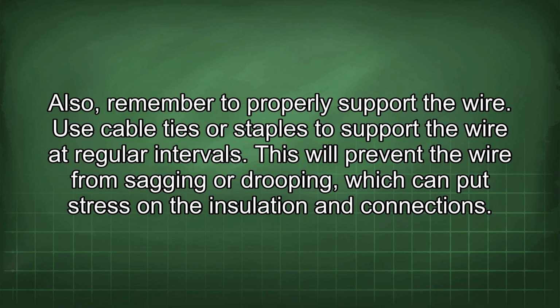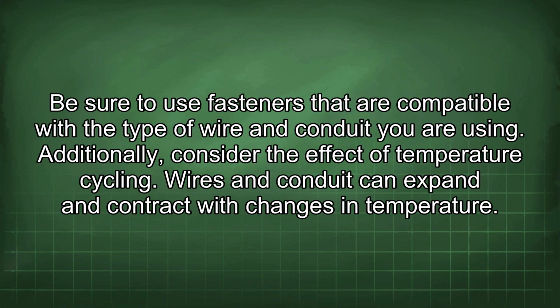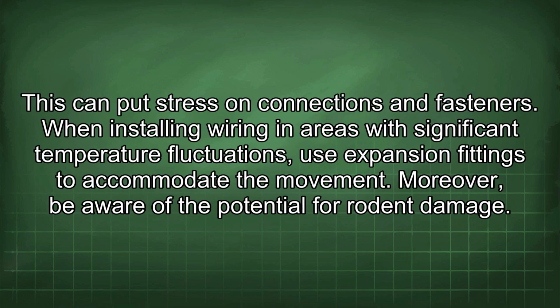Use cable ties or staples to support the wire at regular intervals. This will prevent the wire from sagging or drooping, which can put stress on the insulation and connections. Be sure to use fasteners that are compatible with the type of wire and conduit you are using. Additionally, consider the effect of temperature cycling. Wires and conduit can expand and contract with changes in temperature. This can put stress on connections and fasteners. When installing wiring in areas with significant temperature fluctuations, use expansion fittings to accommodate the movement.